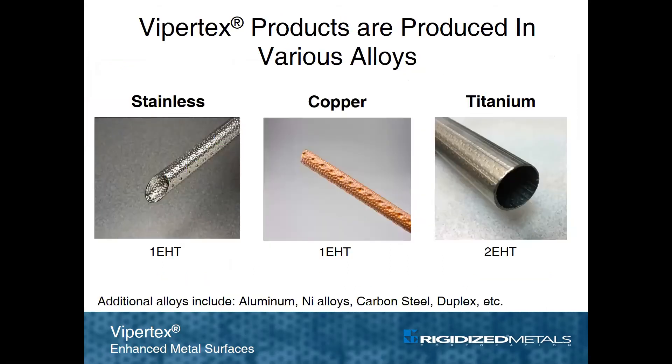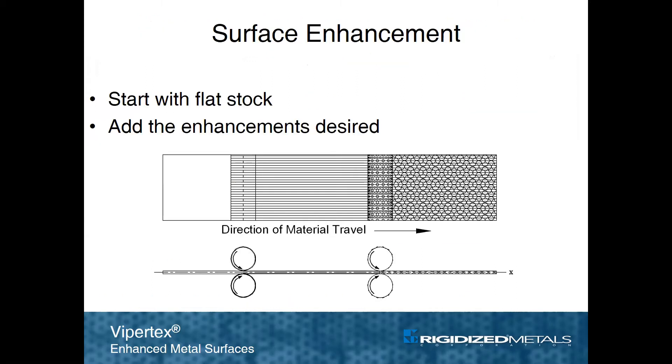Vipertex surfaces can be produced in a variety of alloys including stainless steel, copper, titanium, aluminum, nickel alloys, carbon steel, and others. Vipertex tubes get their enhancement by imparting patterns into metal strip prior to tube welding. Typically, more than one pattern is used to create the complex geometry that is required to optimize fluid flow patterns.